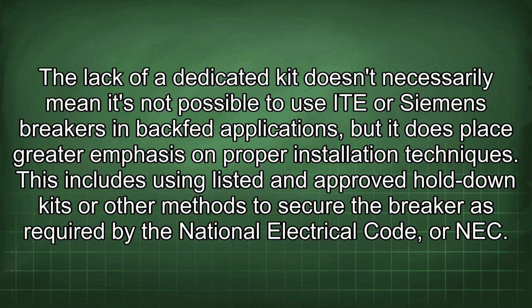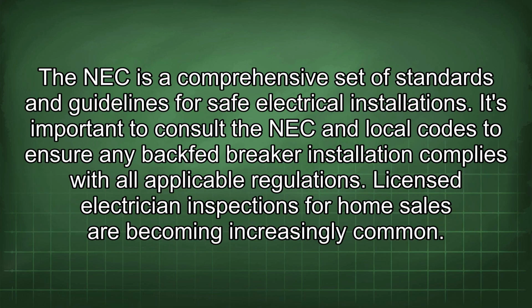The lack of a dedicated kit doesn't necessarily mean it's not possible to use ITE or Siemens breakers in backfed applications, but it does place greater emphasis on proper installation techniques. This includes using listed and approved hold-down kits or other methods to secure the breaker as required by the National Electrical Code, or NEC. The NEC is a comprehensive set of standards and guidelines for safe electrical installations. It's important to consult the NEC and local codes to ensure any backfed breaker installation complies with all applicable regulations.